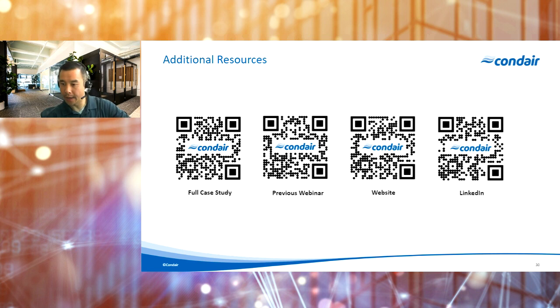Sean, there's a good one here for you. For evaporative cooling, can you analyze the water and give an idea of maintenance intervals and cycles of concentration? Yeah, there are a number of ways that this can be done to calculate cycles of concentration. There are very simple ways. If you go to a media manufacturer, they will typically have their specific parameter limit, say 300 milligrams per liter of calcium. That's the simple way to do it: you divide that number by your input and you have the cycles of concentration. There are more sophisticated ways of doing that. Condair as a company can support that. So I'd say work with your engineer and your media manufacturer to analyze the water, because some of these are a little bit more advanced calculations to get more accurate values.